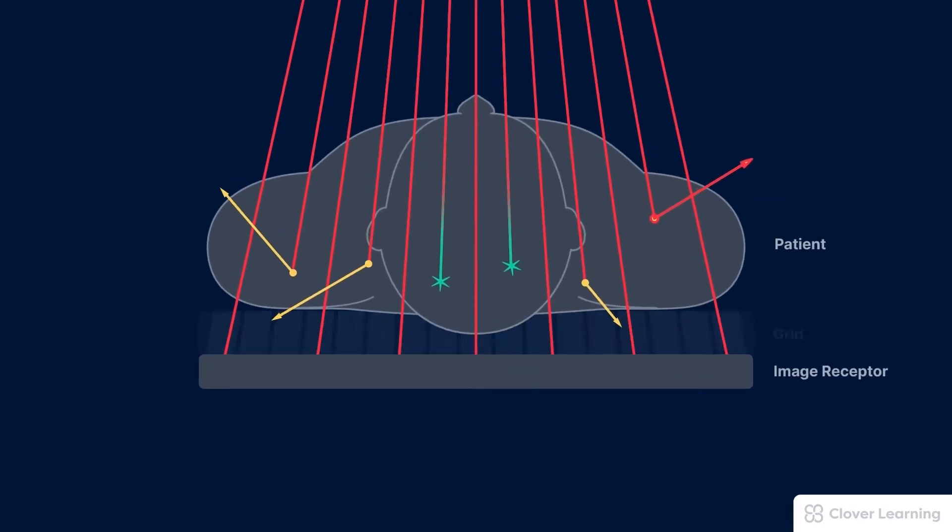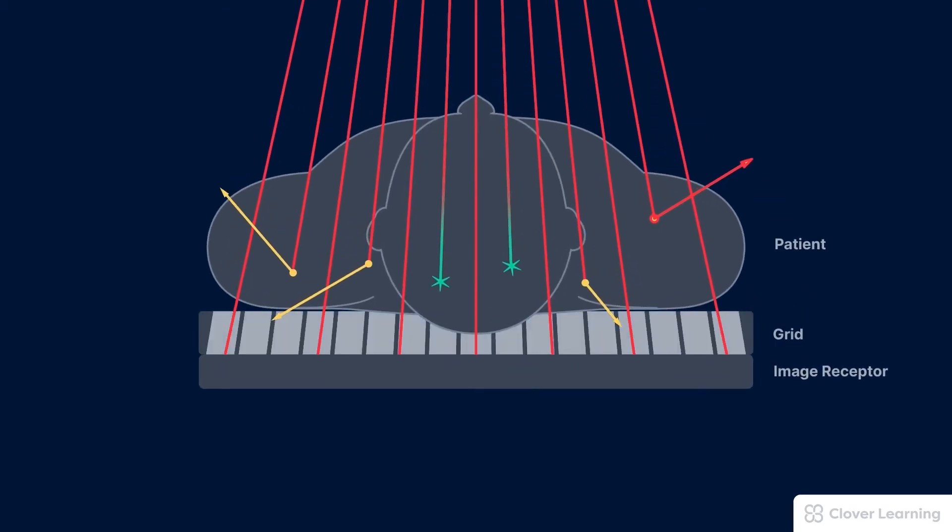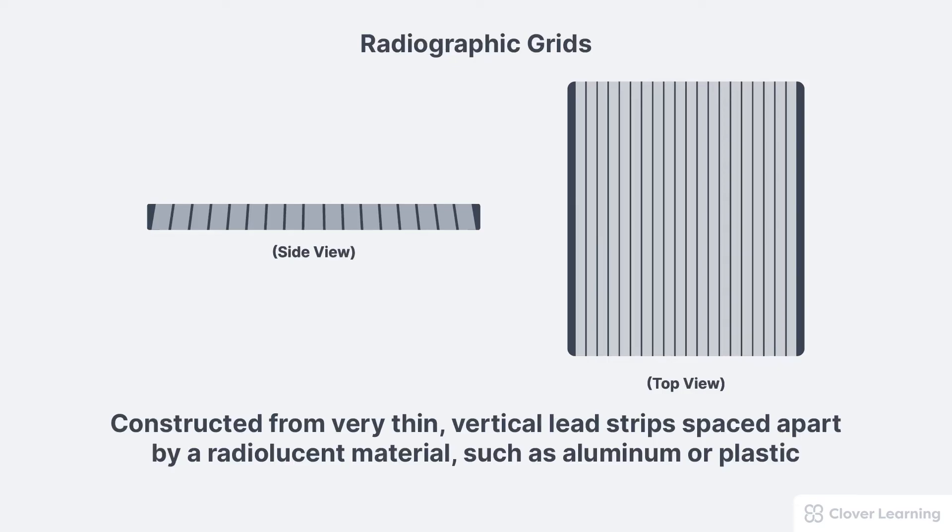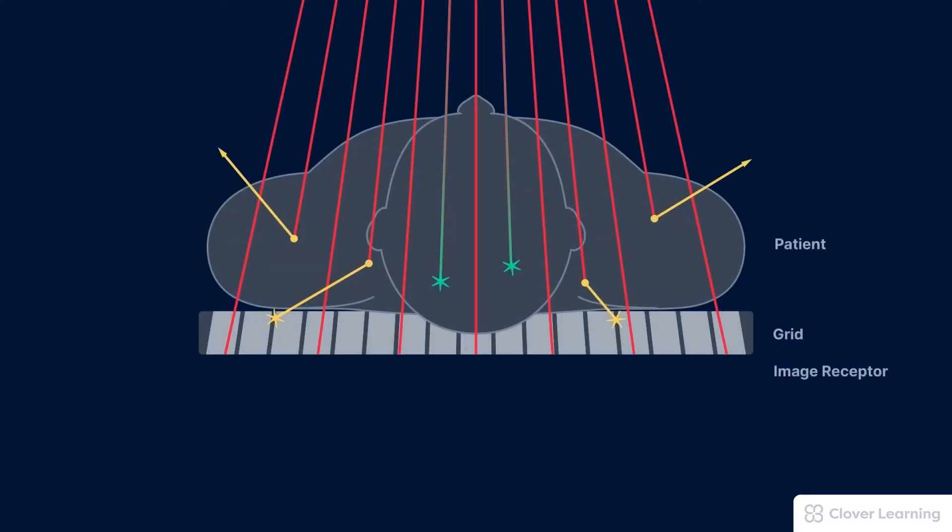So how do grids work? A grid is placed between the patient and the image receptor to absorb scatter before it strikes the image receptor. Grids do not decrease the production of scatter within the patient, but they do remove scatter from the beam before it strikes the image receptor and degrades the image quality. Grids are constructed from very thin vertical lead strips that are spaced apart by a radiolucent material, such as aluminum or plastic. Due to this vertical orientation of the lead strips, transmitted photons from the main beam that carry good information are allowed to pass right through the grid to the image receptor, and that's what we want.